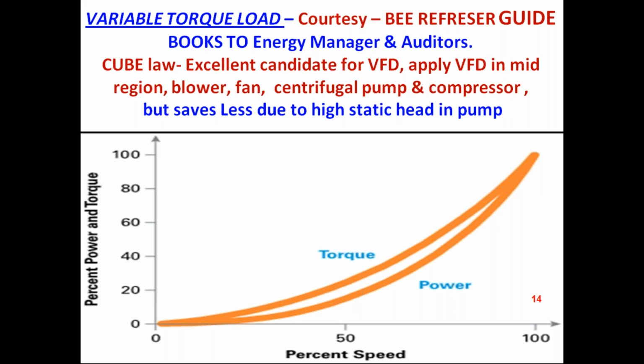You categorize the industry loads into constant torque loads and variable torque loads. Constant power loads are very rare in industries. Most production machines are constant torque loads, and variable torque loads come in the utilities and in some production machines, such as a centrifugal blower, centrifugal fan or axial flow fan. It also follows the same affinity law, as does the centrifugal compressor.